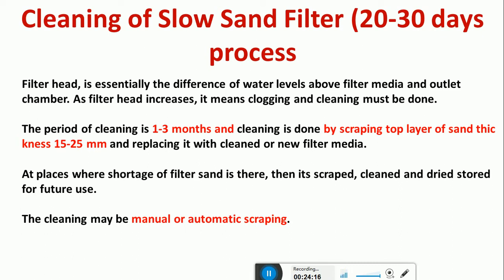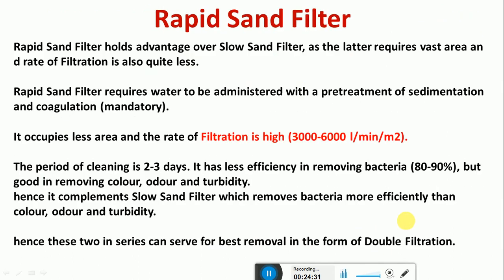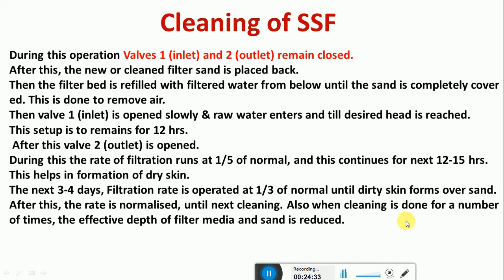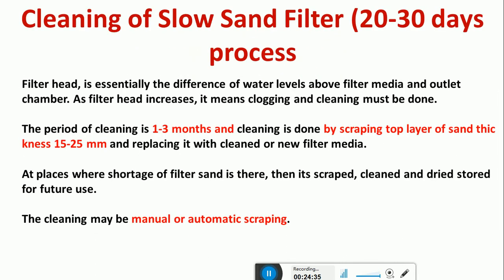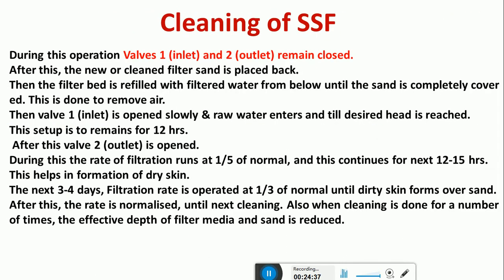But nevertheless, we come to know the cleaning with the help of the filter head. By measuring the head loss to the filter media, the period of cleaning can be known and it is subjected for cleaning. Okay, so here during the cleaning of the slow sand filters, the inlet valve and valves V1 and V2, the outlet valve, remain closed.